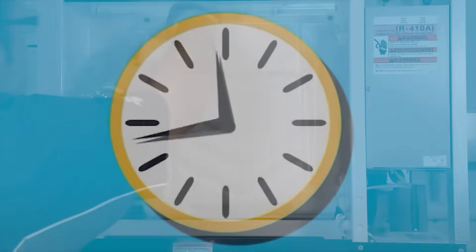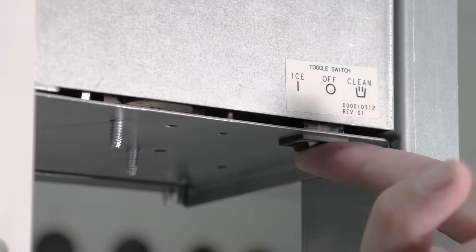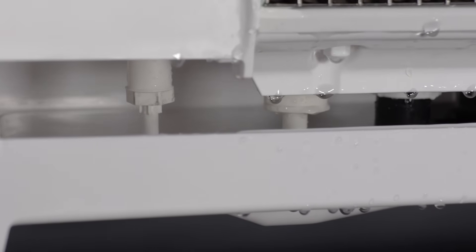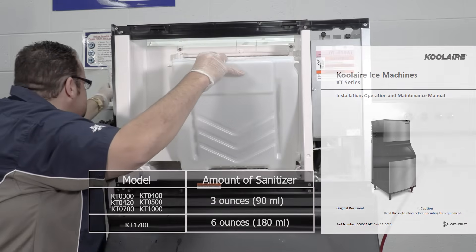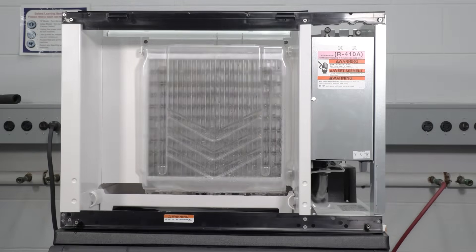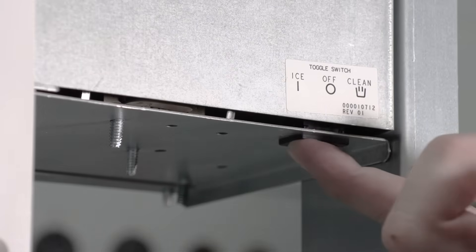Step 12: Replace all the removed components. Step 13: Wait for 20 minutes. Step 14: Reapply power to the ice machine and place the toggle switch in the clean position. Wait until the water trough refills and then add the proper amount of Manitowoc Ice Machine Sanitizer to the water trough. Step 15: After about 24 minutes, the sanitize cycle will be completed. Move the toggle switch to the ice position. This completes the interior cleaning and sanitizing of Koolaire modular ice machines. You should be ready for another six months of efficient operation. Your ice machine is now ready for use.